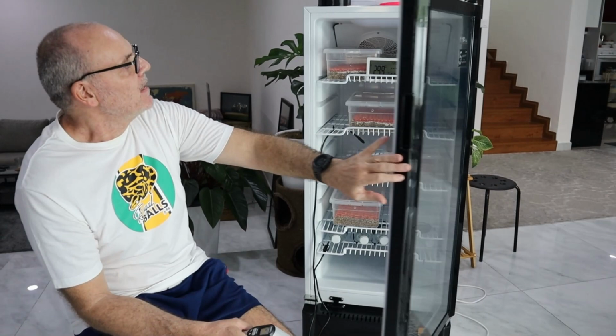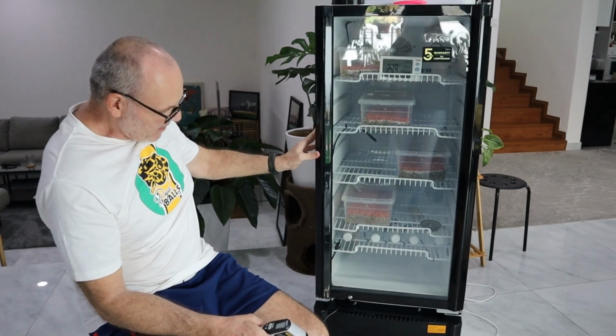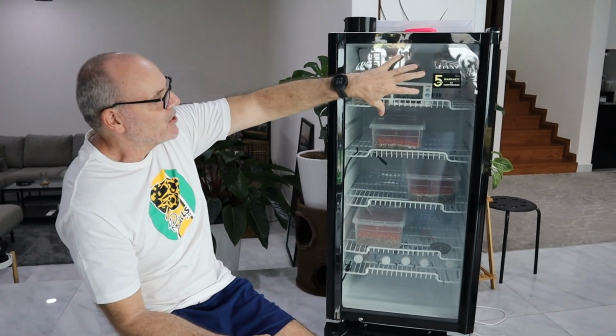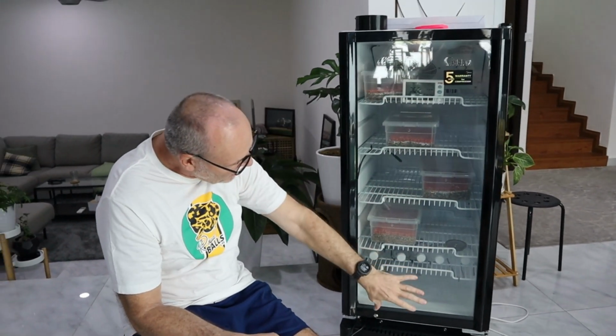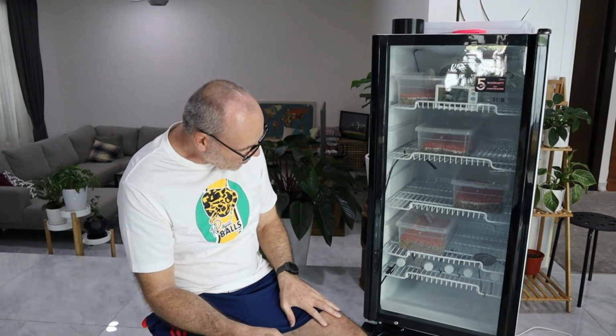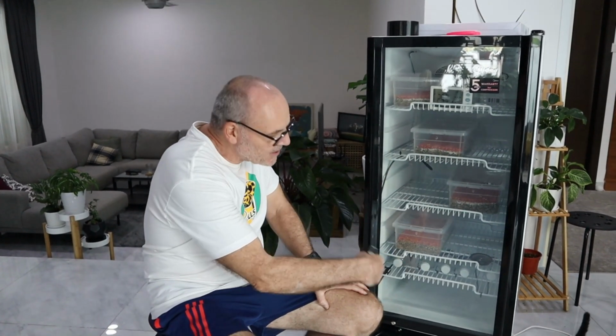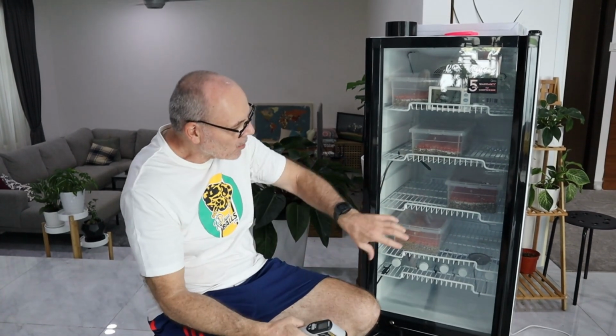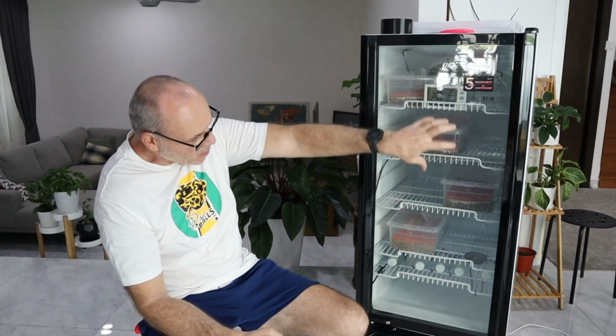So if I find, after playing with this incubator, that I'm getting too much stratification and I'm getting a temperature gradient between the hot air at the top and the cooler air at the bottom, I will install a fan. And what that fan will do is to produce my own convection current that actually disrupts that temperature gradient. So I will cause turbulence in the air, which will enable mixing of the warm air with the cold air and prevent that stratification. So if I need that, I will introduce that after I've figured out how this incubator is running. So we'll do that as the next step if I need to.